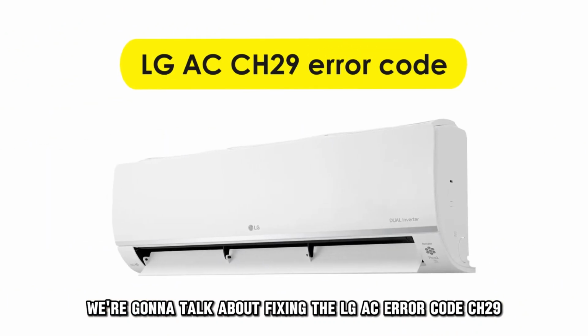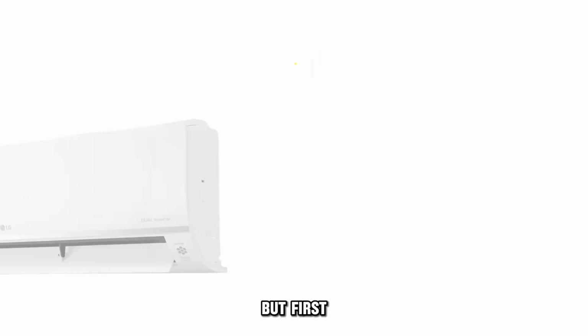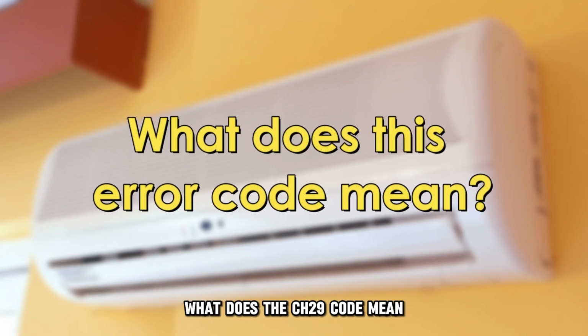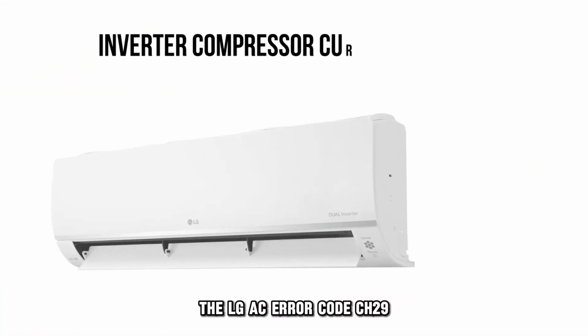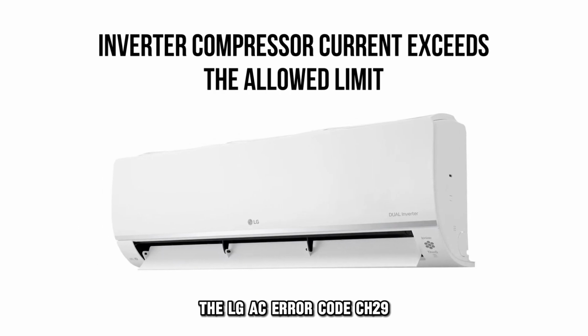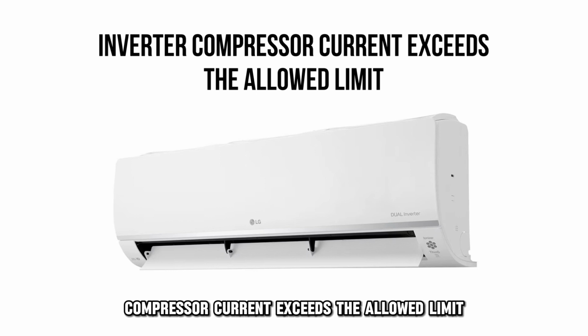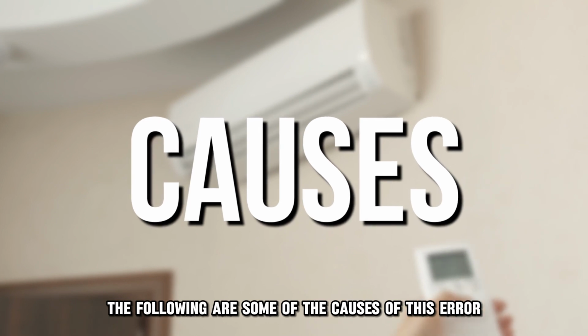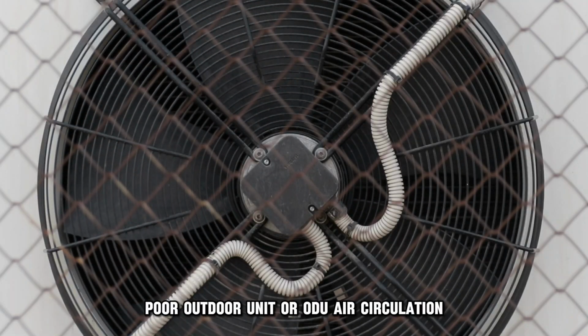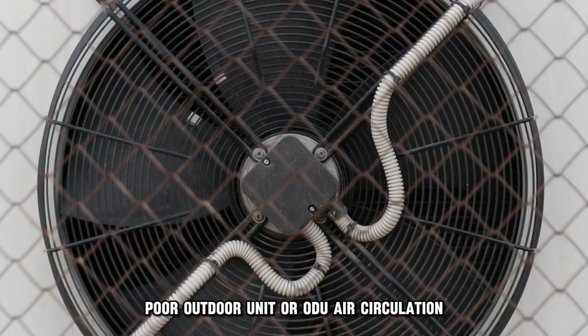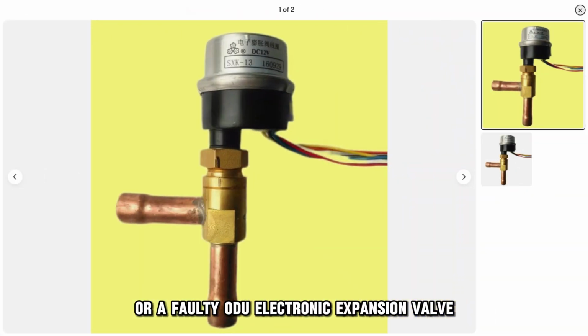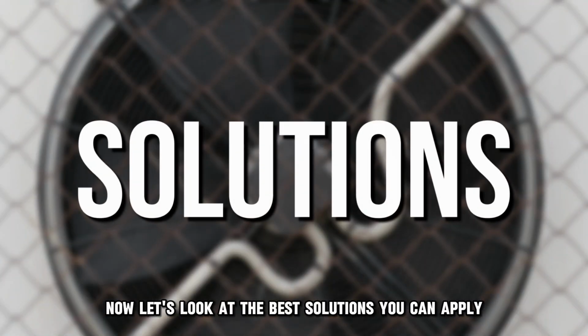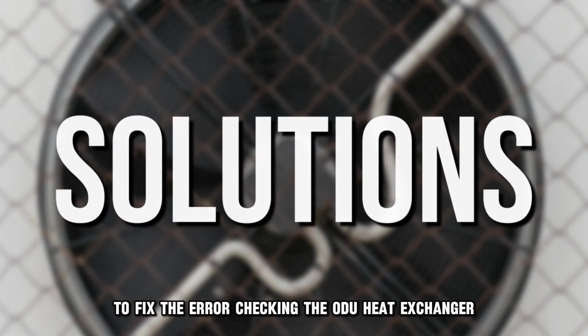But first, what does the CH29 code mean? The LG AC error code CH29 indicates that the inverter compressor current exceeds the allowed limit. The following are some of the causes of this error: poor outdoor unit (ODU) air circulation, or a faulty ODU electronic expansion valve. Now let's look at the best solutions you can apply to fix the error.